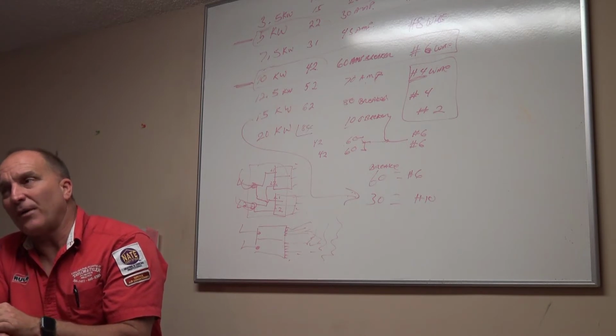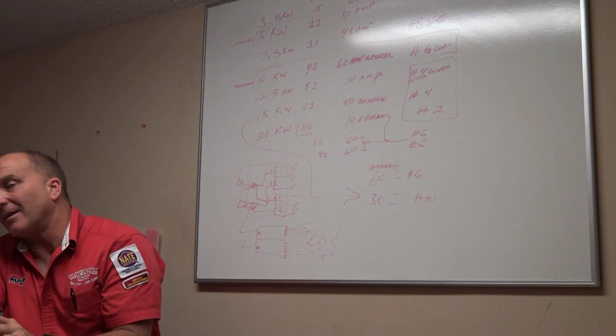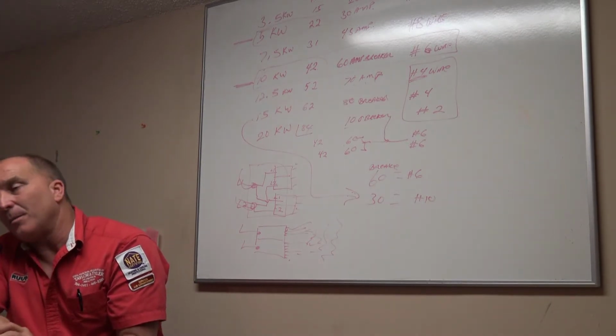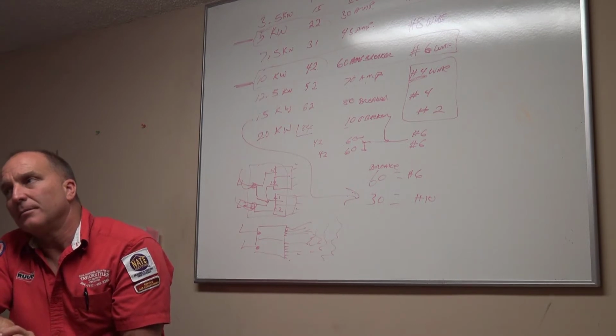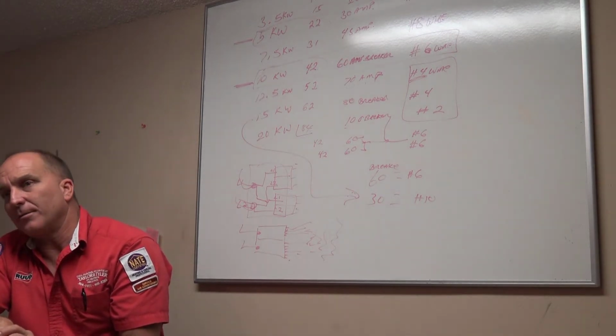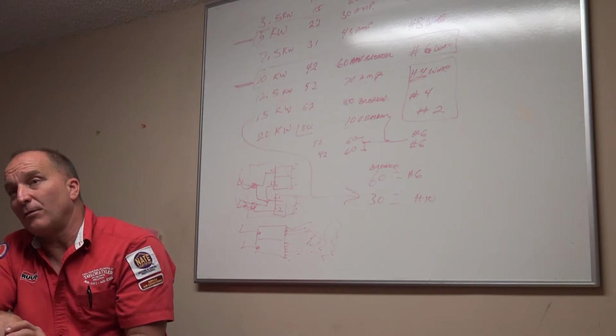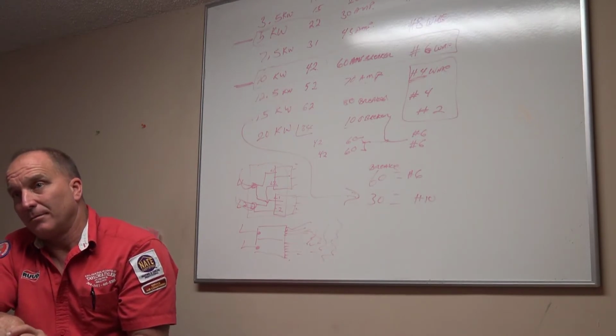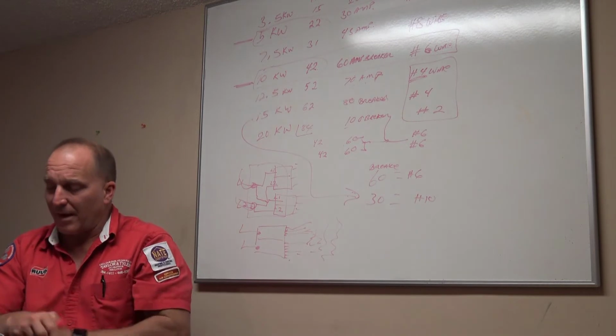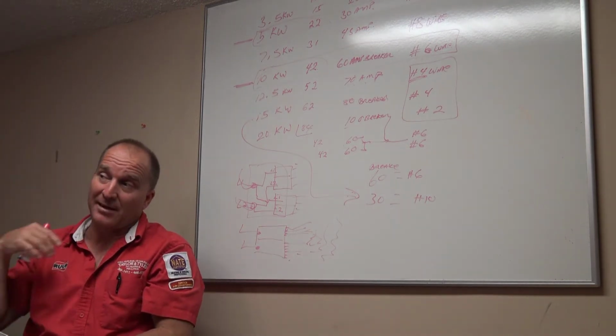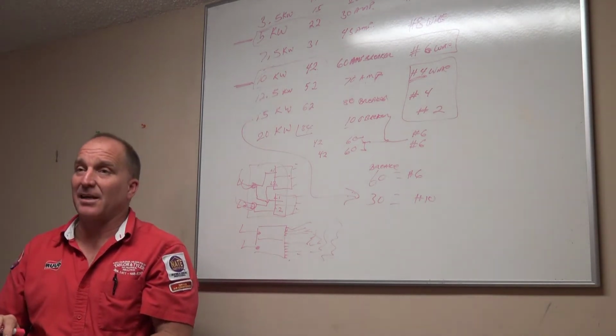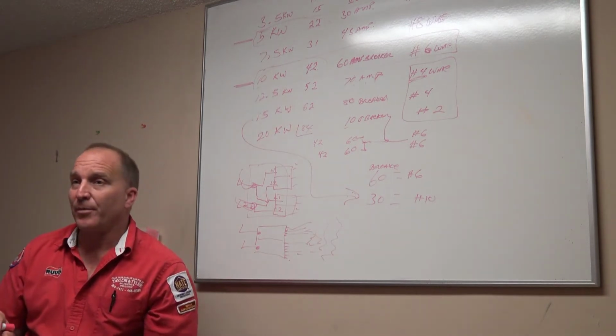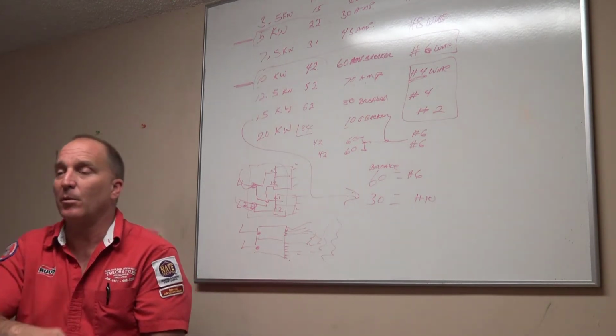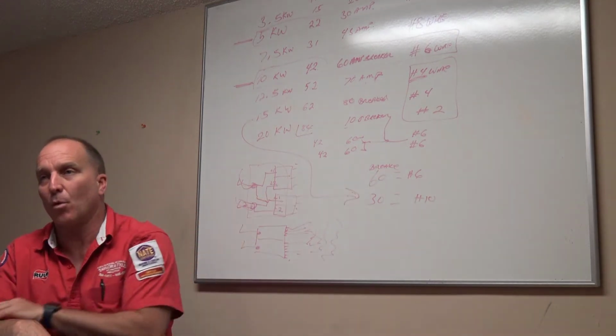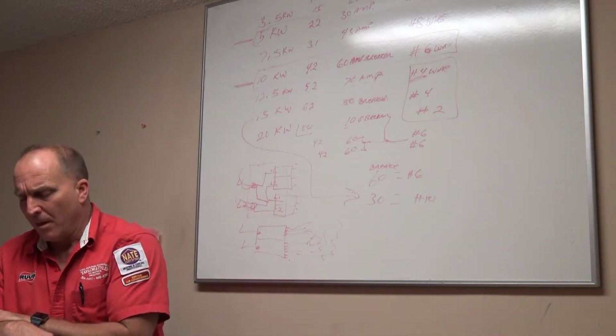Your delta T with the fan in the cooling speed is not going to be probably between 35 and 55, maybe closer to 30. Okay, but it's not going to be 55. Okay, if you got 55, you got dirty evaporator coil. All right. So again, please go over these things that I am telling you, because I went over this exact same thing on the furnace check on the other. The last thing is the other we went through, and we went through the blower chart, and that's where I drew it on the board right there on the furnace check.